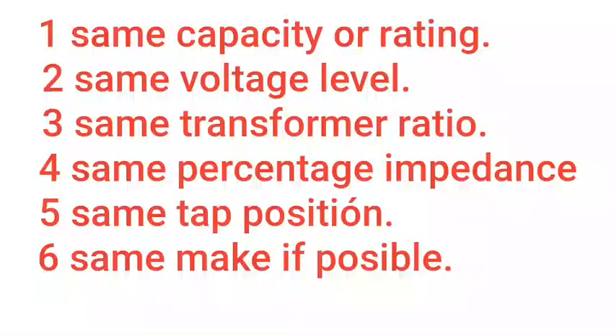What are the factors to be considered before paralleling transformers? Number one is the capacity — the rating of the transformers. It should be the same. If you are paralleling two 60MVA transformers, all of them should be 60MVA. Don't bring in a different-capacity transformer to parallel with one of a different rating.